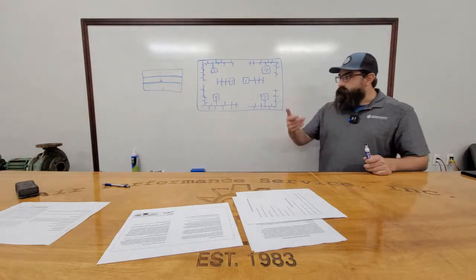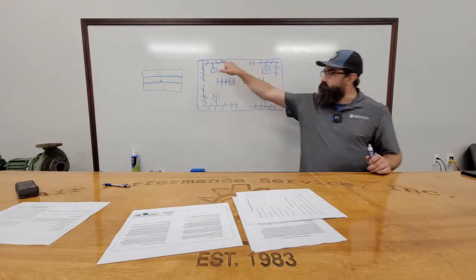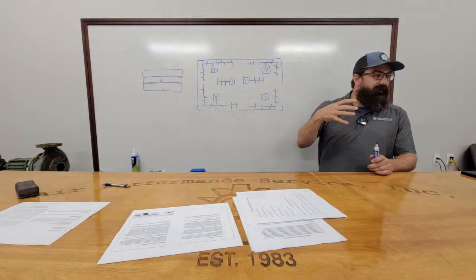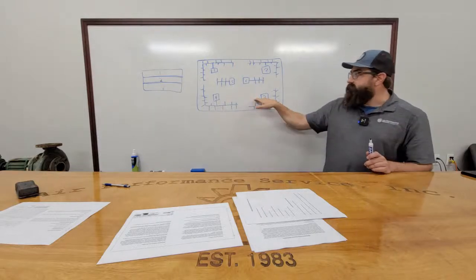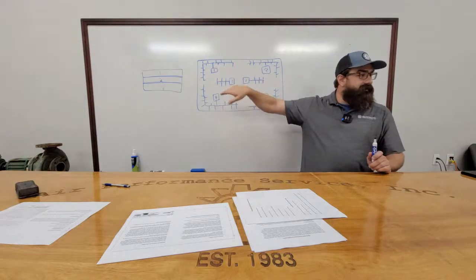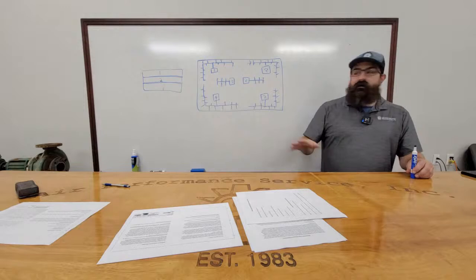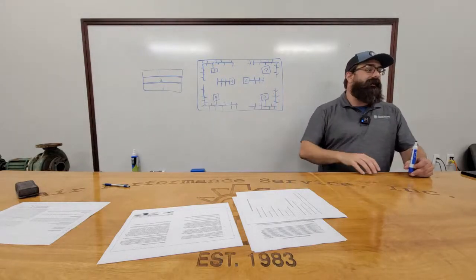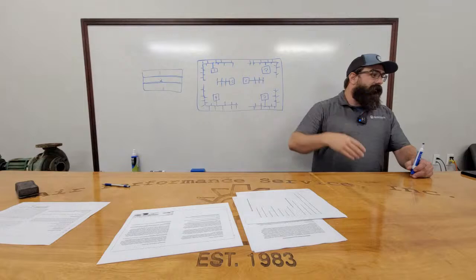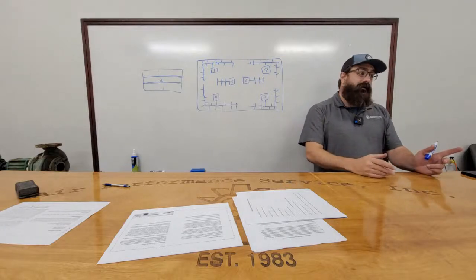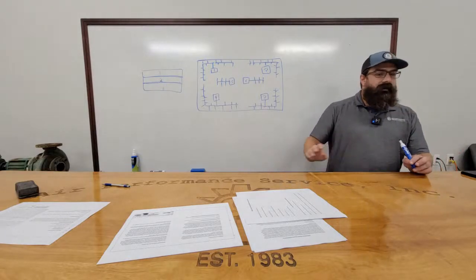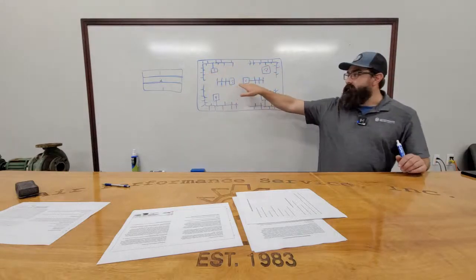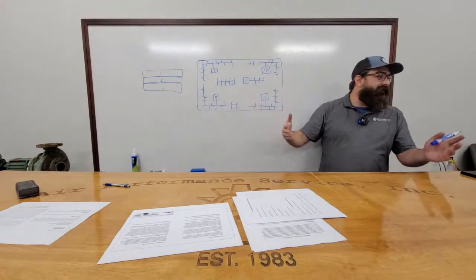Like I was saying, we start this building perimeter first, then we would engage the interior at night when the building is unoccupied. Only this equipment is allowed to run. The interior is not even allowed to run at all. I think there is actually a threshold where it will come on if it gets to a certain temperature, but no, you can override it all day. Yeah, 100%. Let's just say these guys have an unoccupied set point of 85. These may be like 95, something crazy high.